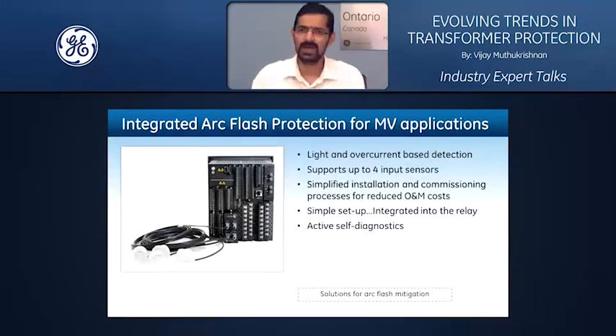Now, the last aspect in terms of protection functionality is the integrated arc flash. I briefly mentioned this is more applicable for medium voltage switchgear. If you have a switchgear lineup that has a combination of motor protection relay, feeder protection relay, and transformer protection relay, your ability to deploy an integrated arc flash module in all of them will become very powerful. It gives you a comprehensive arc flash detection and mitigation strategy in your medium voltage application. So the 845, for example, can support up to 4 optical sensors and detect light, supervised with overcurrent, which is a fast operating instantaneous overcurrent functionality. And it's very simple to set up, and it has built-in self-diagnostics that can let you know when the sensor circuit has any problems.